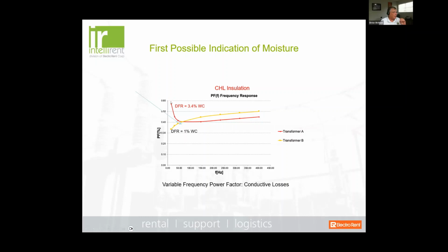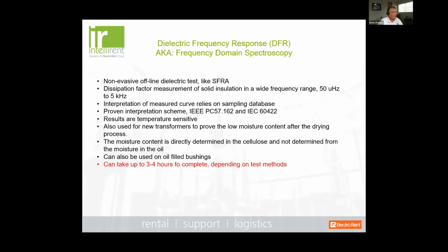okay, in this range, you're showing conductive losses, then it's recommended you do what's called a dielectric frequency response. Okay, and that is, again, a non-invasive test. It's similar to SFRA, but not really. It's looking at either the power factor or the tangent delta, which is identical, similar to power factor, but looking at the other side of the angle. And what we're looking for, over a much extended, larger frequency range, is whether there is excessive moisture in the insulation itself. And that's basically what it's looking at. It's looking at the percent of moisture in the insulation.